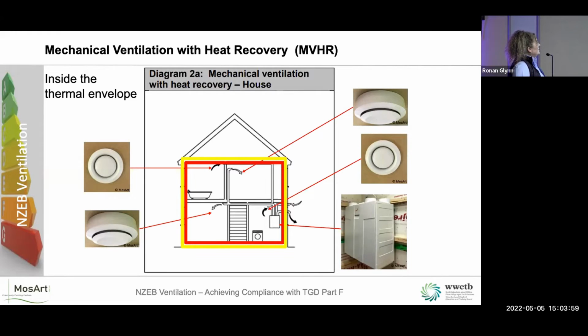So now these ducts here are cold. So we have cold ducts now in a warm space. So these have to be insulated as well. So how it works is it extracts the 20 degree heat into the MVHR unit. It recovers up to 90%. So if we have 20 degree heat, we'll say 18 degrees it can recover. So now it can supply 18 degree heat into the supply rooms, and you're only exhausting 2 degrees.